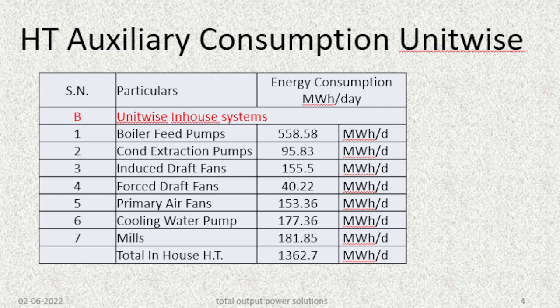The high-tension auxiliary consumption unit-wise was also noted. The unit-wise in-house systems include boiler feed pumps, condensate extraction pumps, induced draught fans, FD fans, primary air fans, cooling water pumps, and mills. The total in-house high-tension auxiliary consumption for one unit was 1362.7 MWh per day per unit.